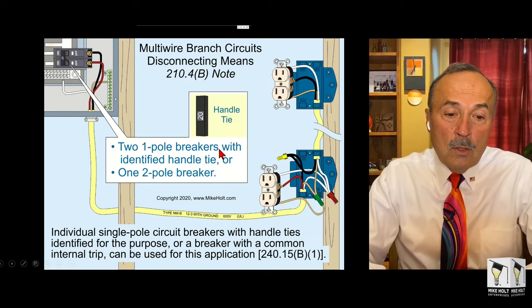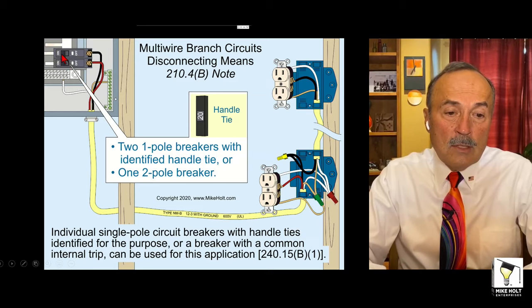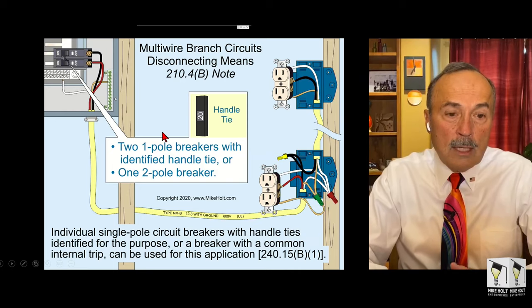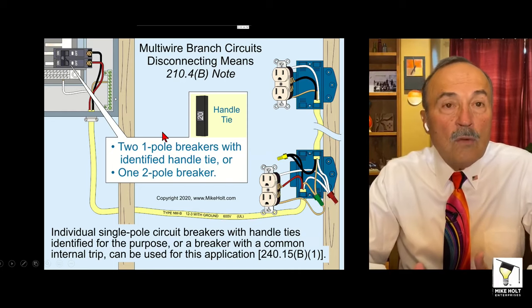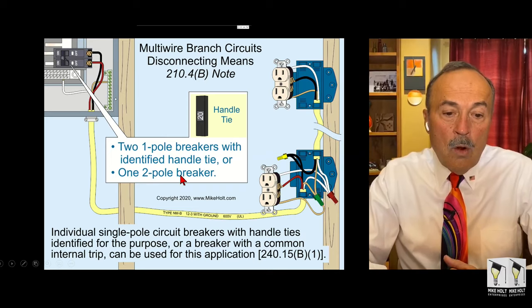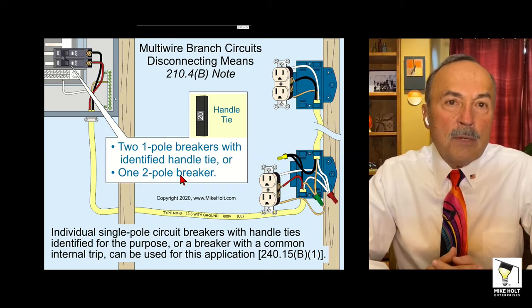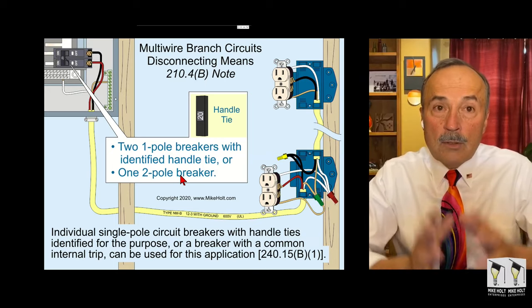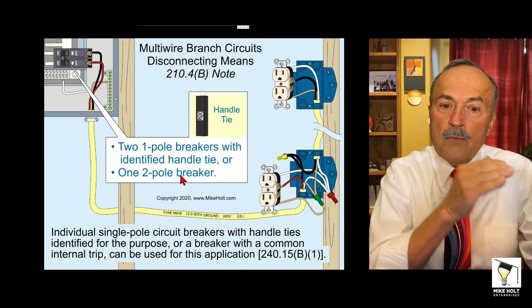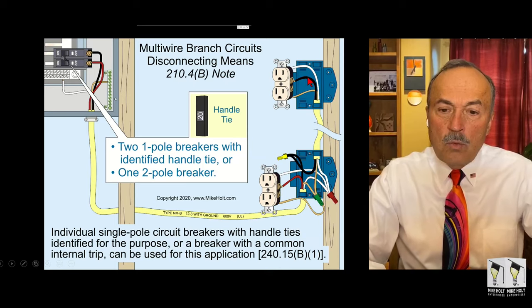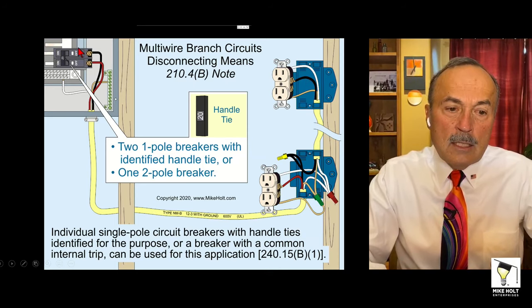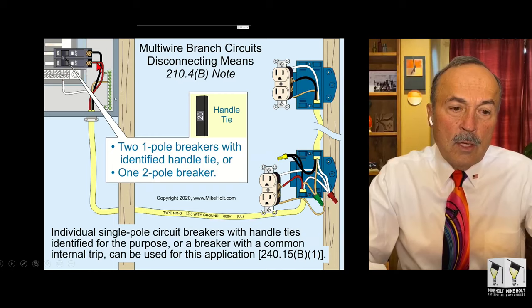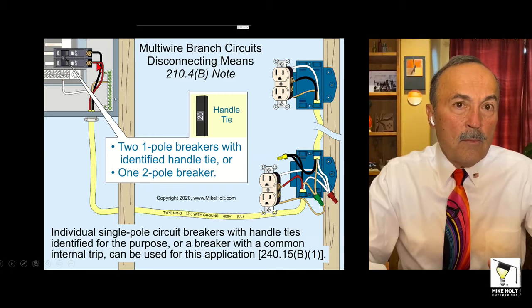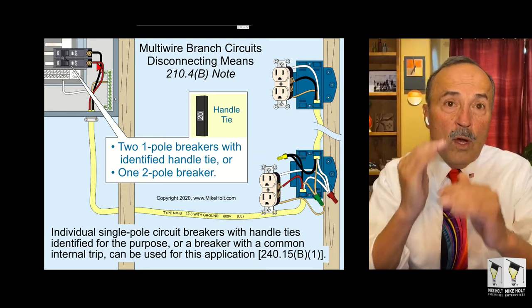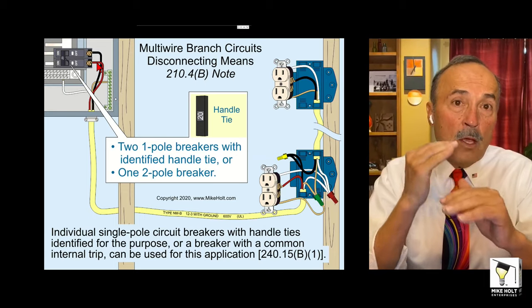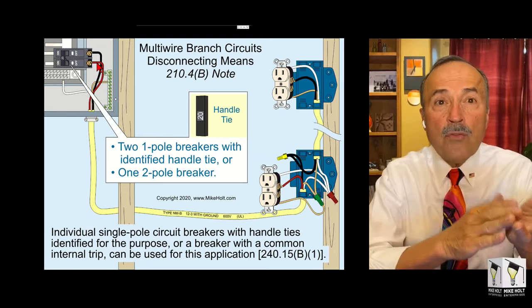It permits two 1-pole breakers with identified handle tie, not a nail and a screw or anything like that, or a piece of 12 wire or 10 wire, or a common trip breaker, like a 2-pole breaker. Okay, so that's a disconnecting means. But let's say there was a fault in this one on the black circuit here, that doesn't mean that when you trip the black circuit here, that the red circuit has to open at all. Some manufacturers have breakers where one phase of the two or the three opens, it actually will open up all three phases.